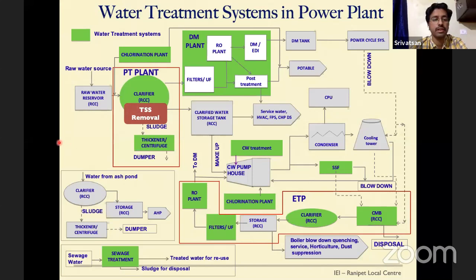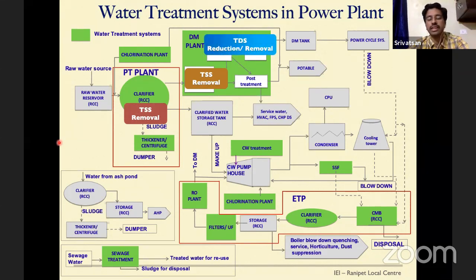In the pre-treatment plant, the suspended solids are removed, and dissolved solids are passed out, so not all processes require removal of dissolved solids. Then in the DM plant, we need to further remove the suspended solids to be suitable for the downstream application of removal of dissolved solids. So the pre-treatment plant and DM plant involve total suspended solids removal. Then there is TDS removal, total dissolved solids removal, which happens in two stages.